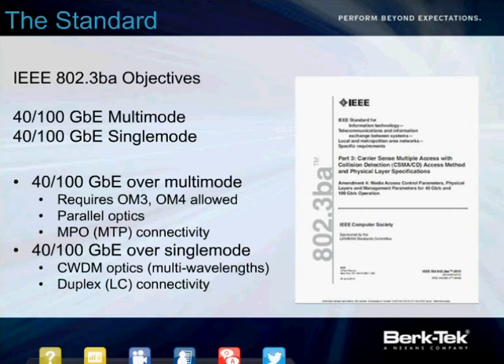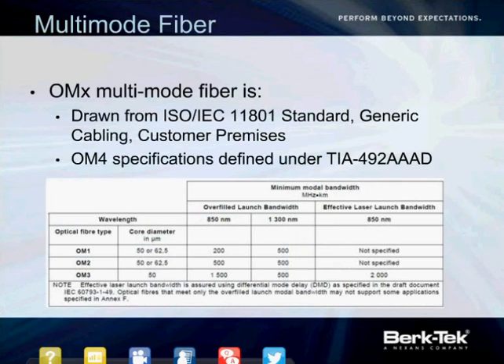Here are the parameters. On the multimode side, notice the third bullet point: MPO — otherwise known as MTP — connectivity and parallel optics. The multimode portion uses multiple fibers each way, each at 10 gigabit. Single mode is CWDM, coarse wavelength division multiplexing — multiple wavelengths over a single fiber. Single mode typically uses LC or SC connectivity, whereas multimode uses the MPO connector. You always hear about OM1, OM2, OM3 — if you're writing a spec and don't know where it comes from, here it is.